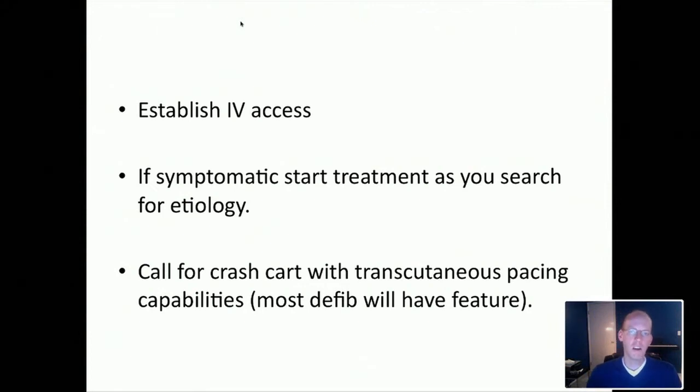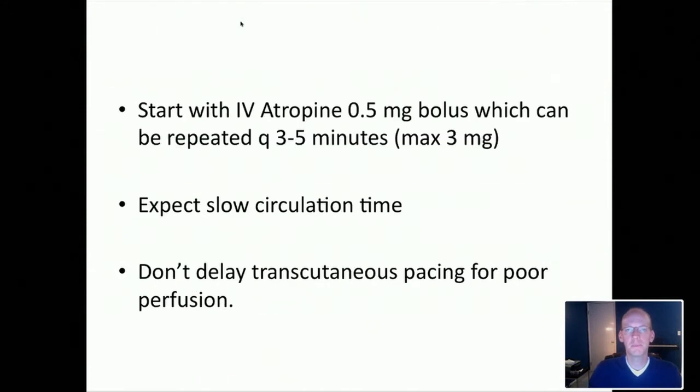So go ahead and call for the crash cart. The crash cart is going to bring resources. It's also going to give you the ability to do transcutaneous pacing, which is in the algorithm. And you should know that most defibrillators also have the pacemaker feature associated with it. Now, these are the ones that are on crash carts. AEDs obviously don't have pacemaker function, so you're going to need to get a real pacer defibrillator. Once again, check your local hospital to know what is available for you. This would be part of knowing your environment.